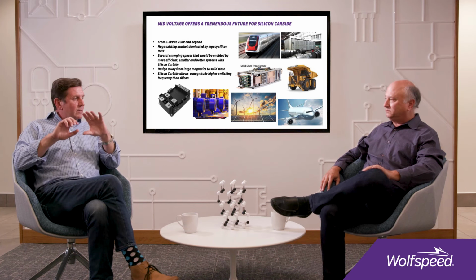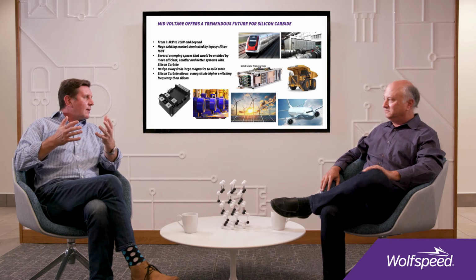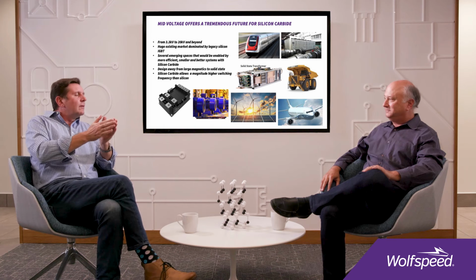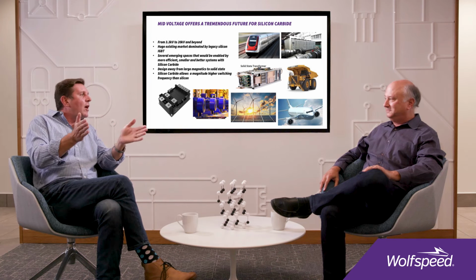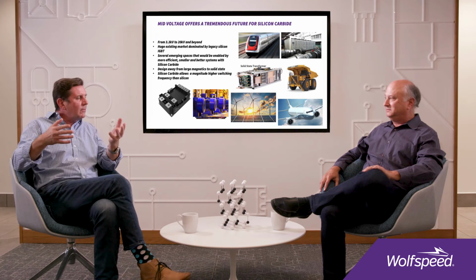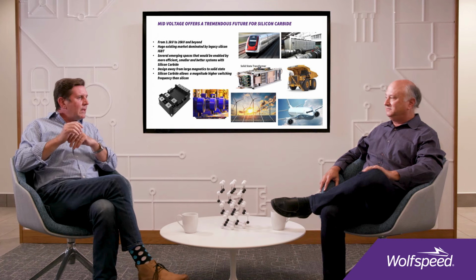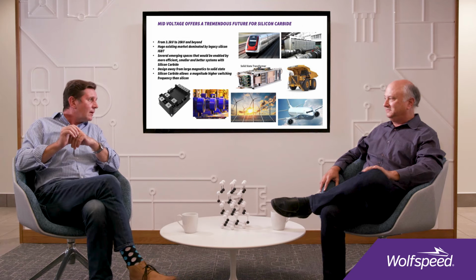Just generally, operating in DC is great for silicon carbide. Yes, you have to have some sort of transformer somewhere for isolation, a one-to-one transformer to convert. But when we can manipulate and switch mode DC to DC and exploit switching frequency, we reduce the size of all those magnetics, caps, and cooling — whether it's a 2 kilowatt server power supply or a 20 megawatt solid state grid-tied system, the principles are pretty much the same.